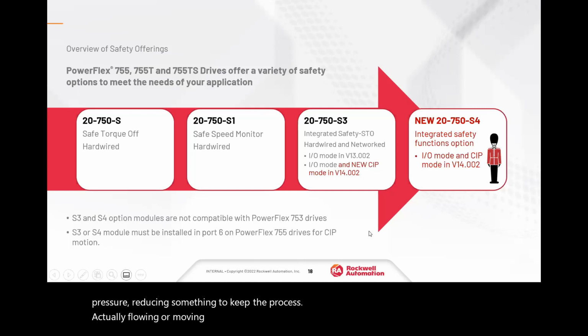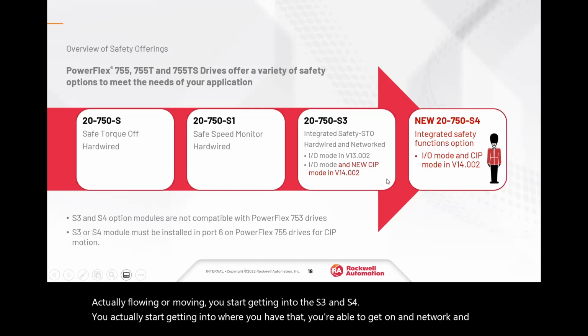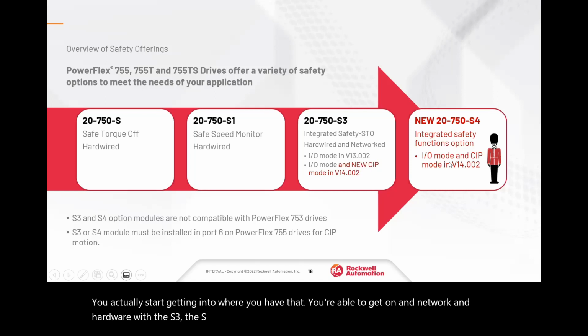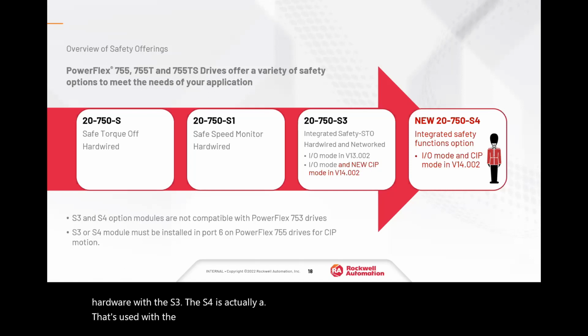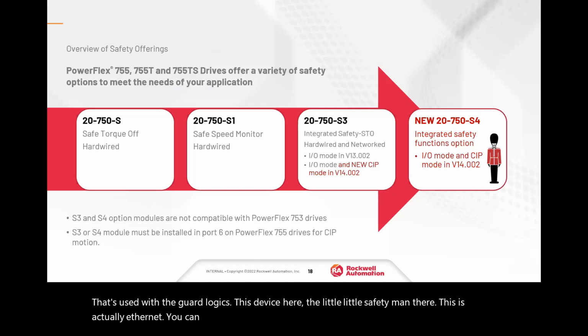You start getting into the S3 and S4. You actually start getting into where you're able to get on the network and hardwire with the S3. The S4 is used with the GuardLogix. This device here, you see the little safety man there, this is actually Ethernet. You can connect up through Ethernet using a GuardLogix controller and actually control and keep the drive secure through that S4 option.